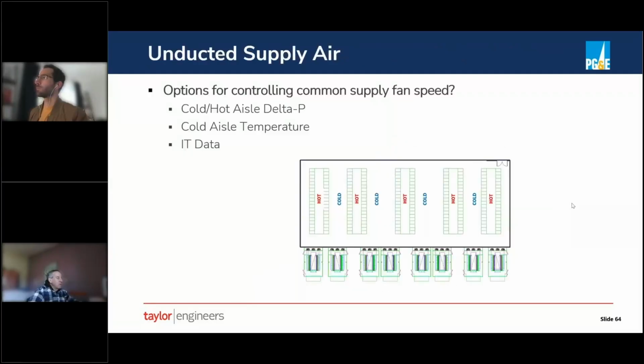So here's the more modern incarnation of a lot of the air cooling, this flooded aisle concept, where you're just supplying air into the space, which effectively makes the whole space a cold aisle. The hot aisles are contained with doors and walls so that the only air path is basically from the cold aisle through the servers back into the hot aisles. What this isn't showing is that there's usually a ceiling. The hot aisles are connected to the ceiling, and then the ceiling is returned back to the air handlers.